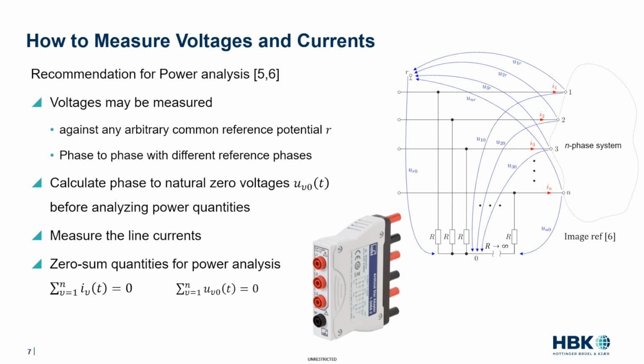And natural zero voltages are the voltages which could be measured against such an ideal artificial star point, which is a nicely balanced star point with equal resistances. And therefore, not only the currents which are going into the N-phase system sum up to zero due to Kirchhoff's law, but also the voltages measured against such an artificial star point. So as just mentioned, in practical measurements, there are a lot of different ways to measure against an arbitrary potential. This could be, in practical applications, the neutral conductor, ground, star point of the machine. There are a lot of different possibilities. But in order to make sure to calculate consistent quantities, not only for instantaneous and active power, but also for apparent and reactive power, in the first step, it's always useful to calculate natural zero voltages, which of course sum up to zero.